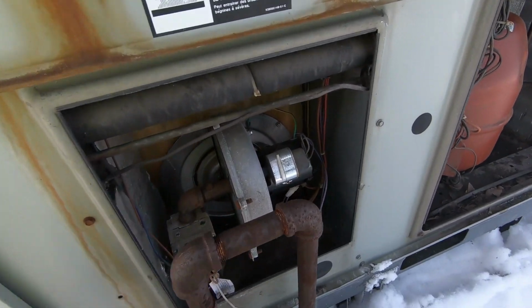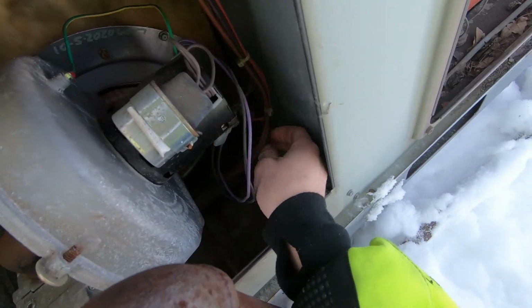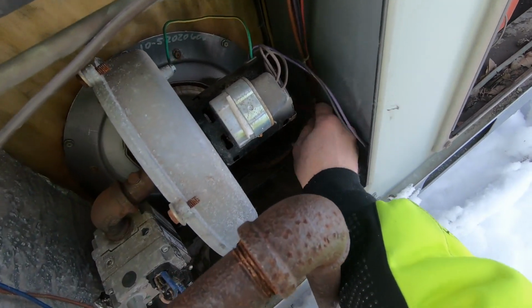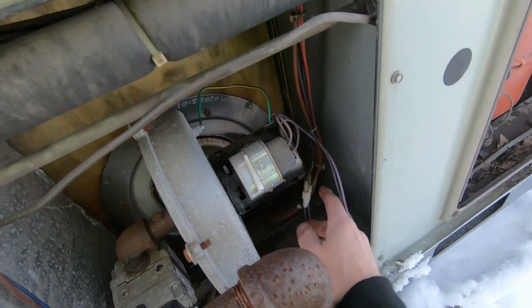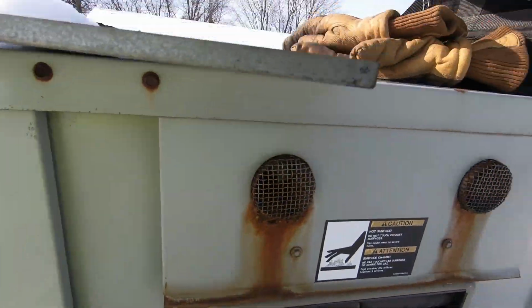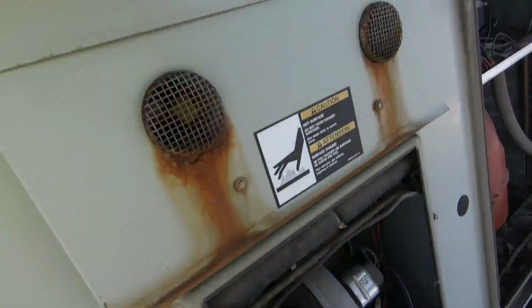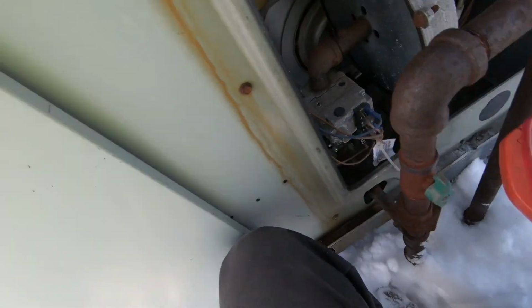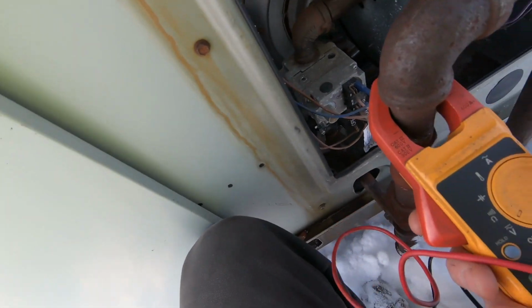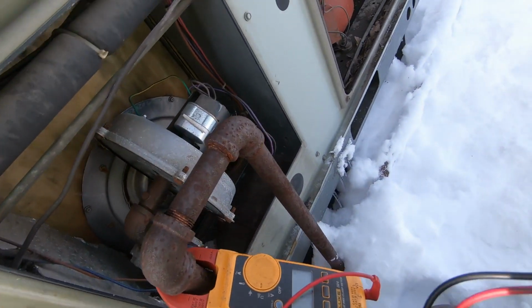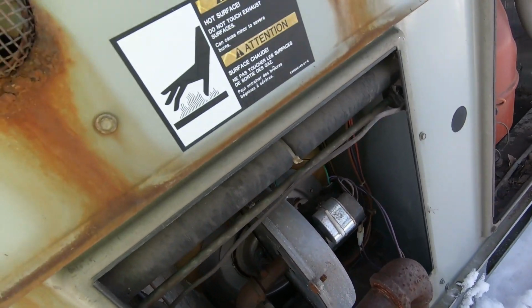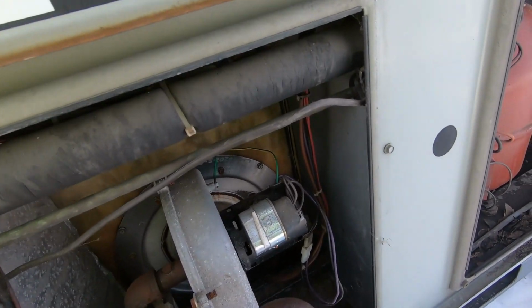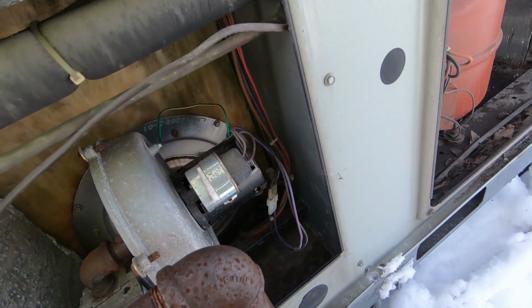All right, guys, I tested the igniter. I'm getting 890 ohms, so it is no good. I did cycle it through just to confirm I had voltage at the igniter, which I did. I also had voltage at the gas valve and smelled gas coming out when it tried to ignite. Let me get my camera set up. I'll show you with the meter.